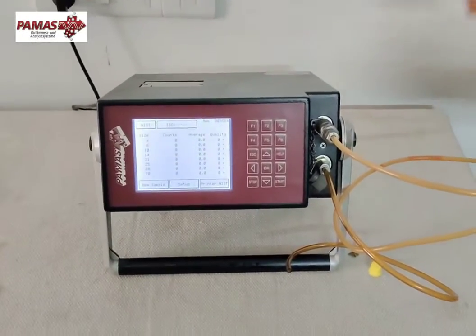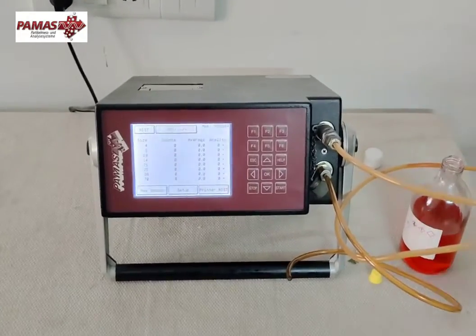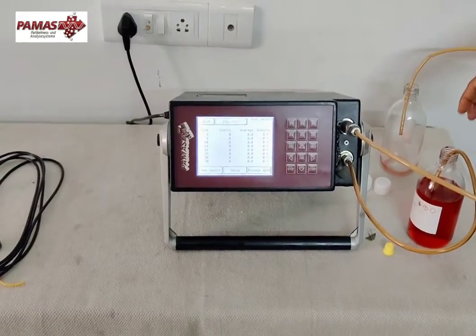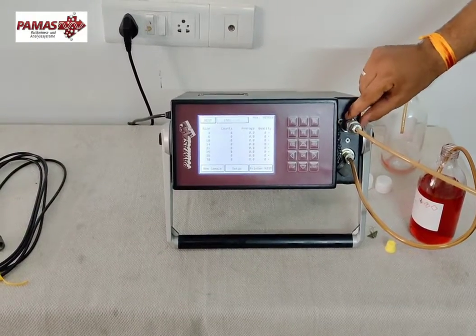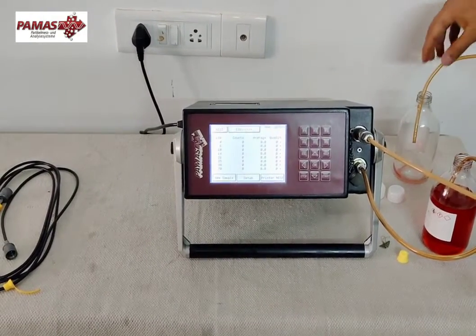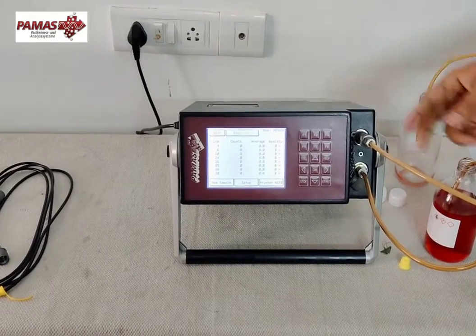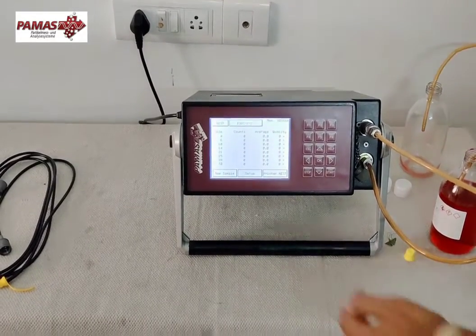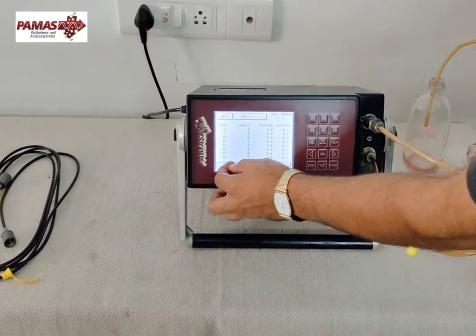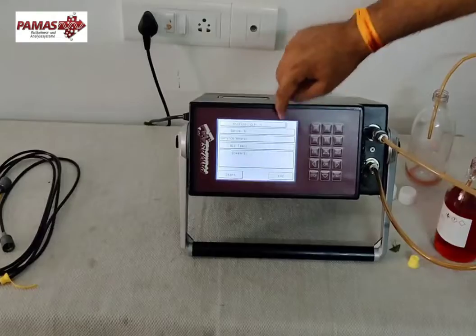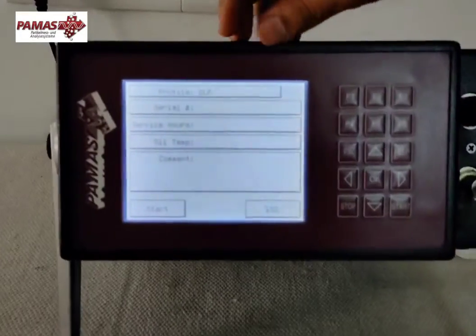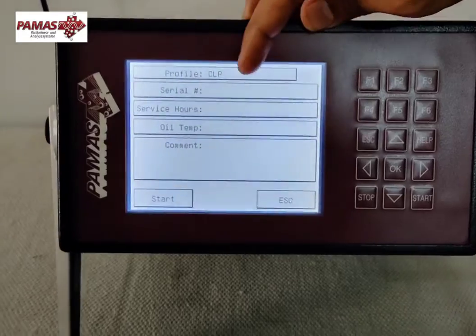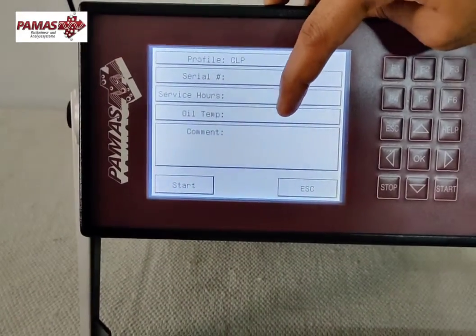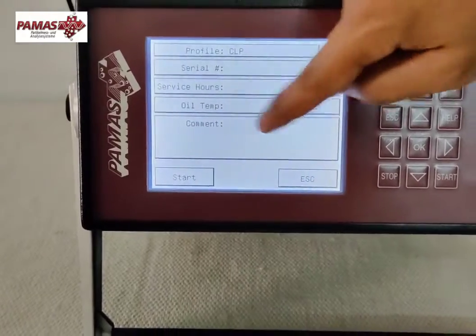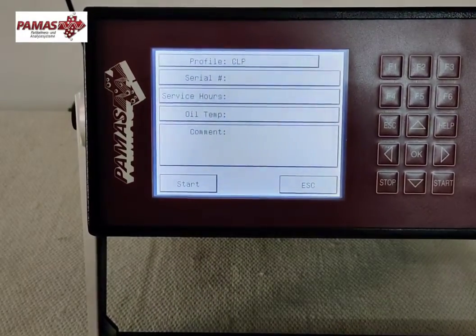Here I have one sample bottle. So now I'm just starting the one measurement. So now what we have done here, we simply connect these two hoses to the system, and one goes to the sample bottle, another goes to the waste bottle. So we are collecting the output in a waste bottle. So what we will do, we will just simply start the measurement here. On this screen you can see we can put all sorts of information regarding our sample, like what kind of sample we are using, what the service hours are, what the temperature is, and all these things. If any special comment is required, we will put it here and it will come onto our print as well.